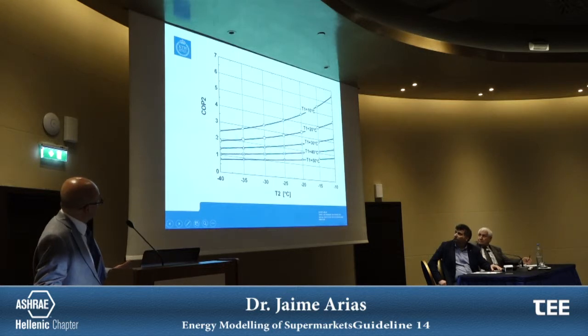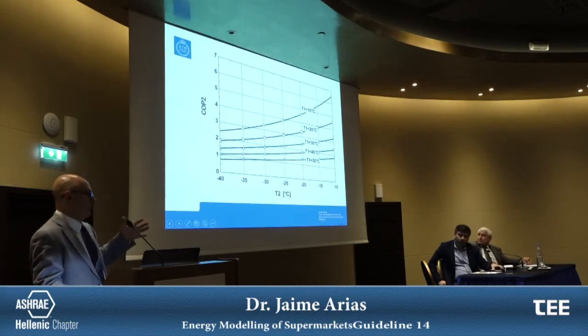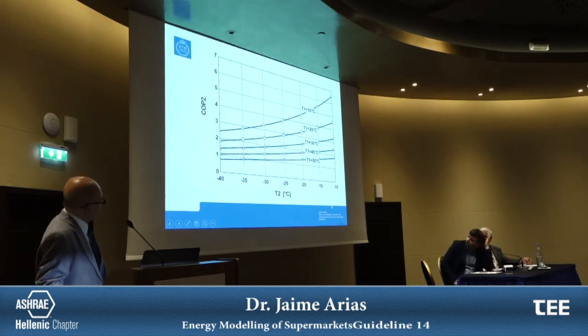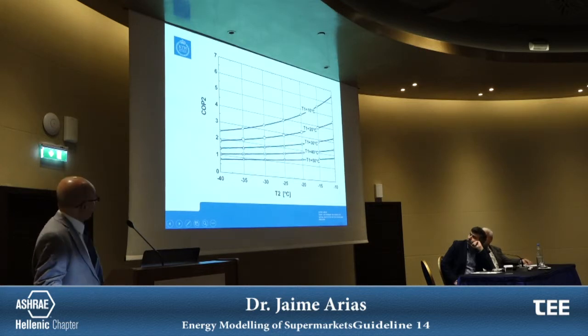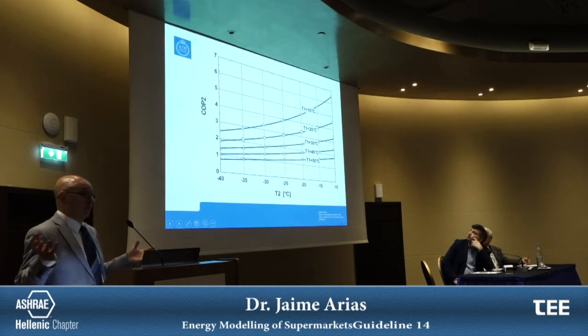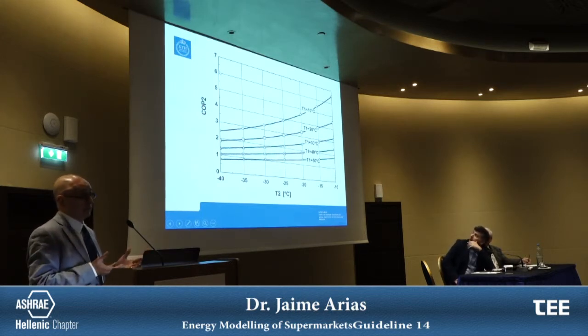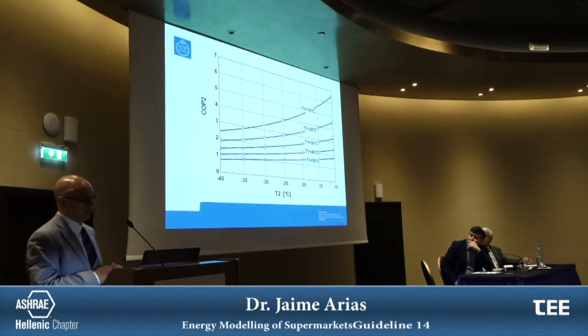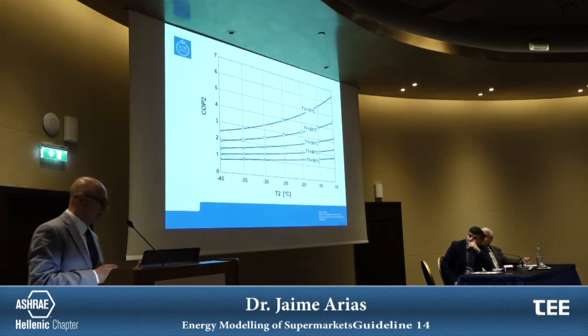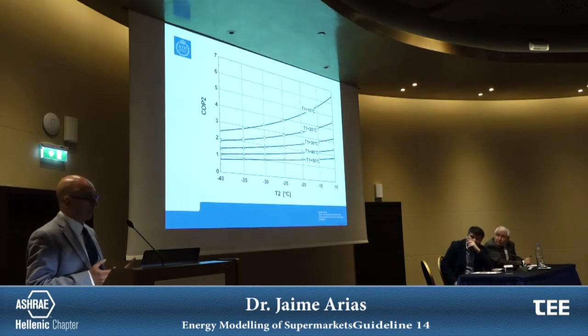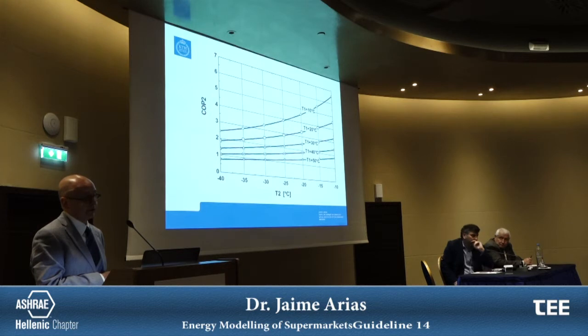So we have a COP of about 2.3. So if now, instead of this, you have floating condensing, I mean, if we are in the winter when we have a low outer temperature, with the same evaporation temperature, and if we say 10 Celsius degrees, the COP increases to a value higher than 6. And of course, for the same cooling demand, you will save a lot of the electricity you use for your compressor. So this was the main idea when we started looking at and implementing this floating condensing. We installed another system we call EcoPump, in which we combine the heat recovery and the floating condensing with very good results. And I will show you one example later.